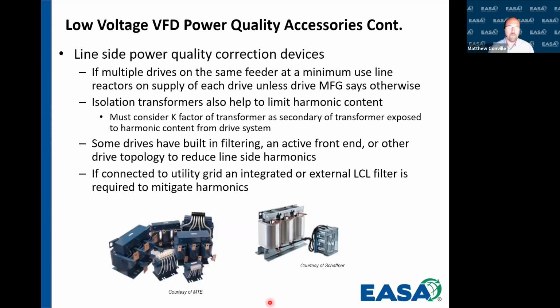So what can we do to fix it on the line side? If we have multiple drives on the same feeder, at a minimum, we need to use line reactors on the supply of each drive, unless the drive manufacturer says otherwise. There are only a few instances that I can think of where a line reactor wouldn't be of some benefit. An isolation transformer would be great, and it also helps limit the harmonic content quite a bit. The problem with that is they're big, right? And then you have losses associated with those, and then you have inrush associated with those. So it may not always be feasible, and they're expensive. If we do use an isolation transformer, we want to ensure that it has the appropriate K factor rating. The easiest way to remember it is, if you're specifying a transformer for a drive, buy a drive isolation transformer.